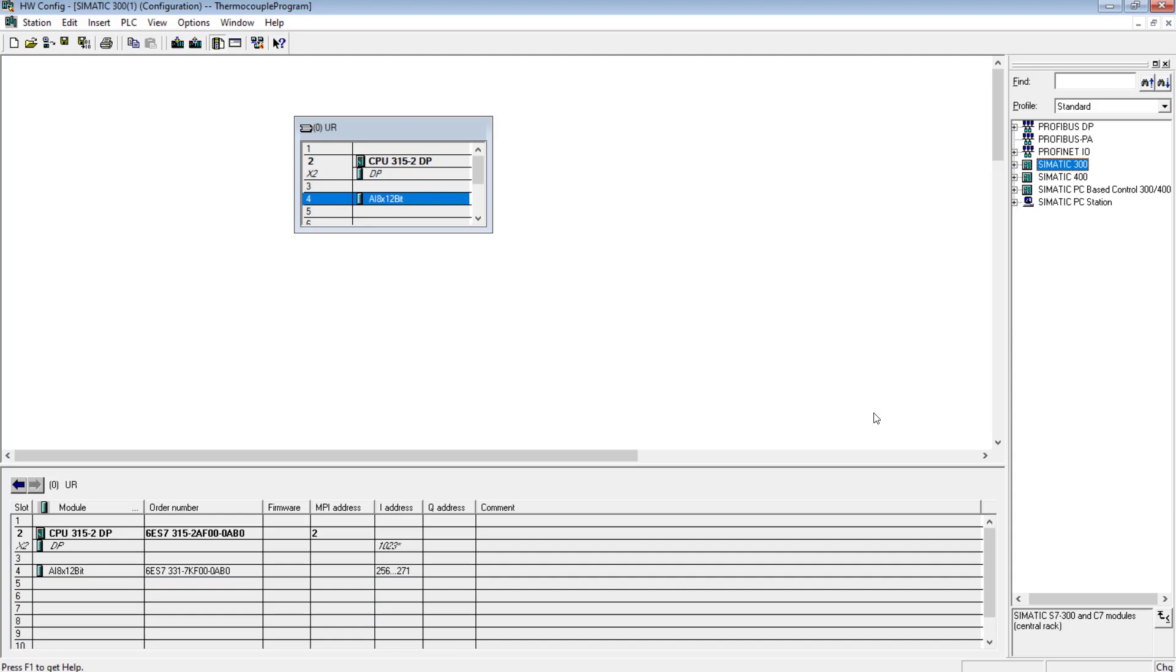Normally it happens that in the field, the thermocouple wires are wired into a temperature controller. The voltage value, the millivolts that are being produced in the thermocouple due to temperature change, are being fed to a temperature controller and the temperature controller in turn gives the 4 to 20 milliamp pair to the PLC analog input card.